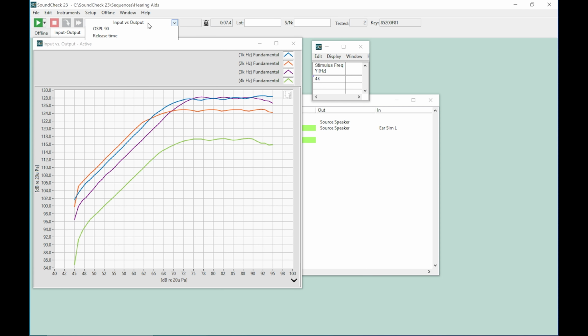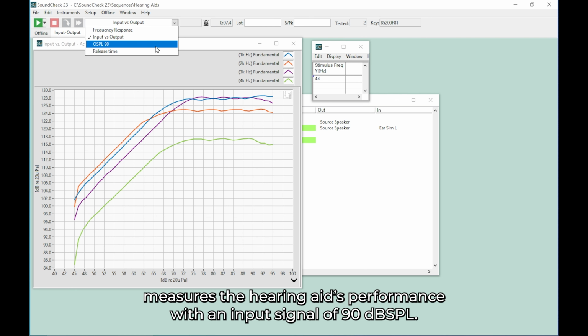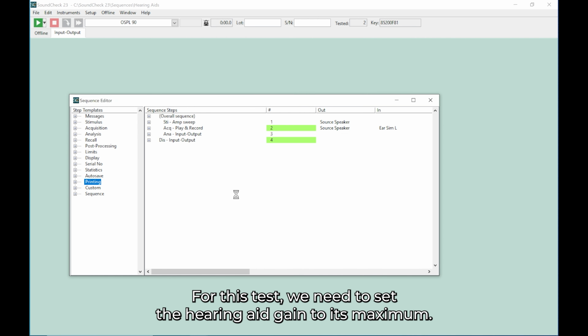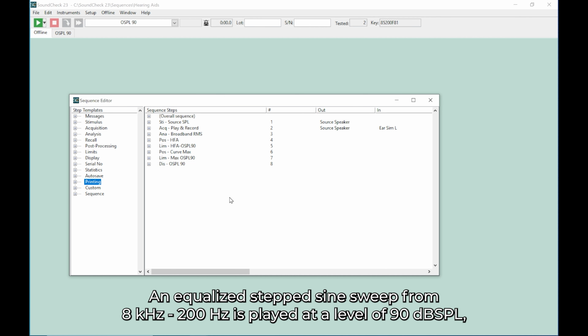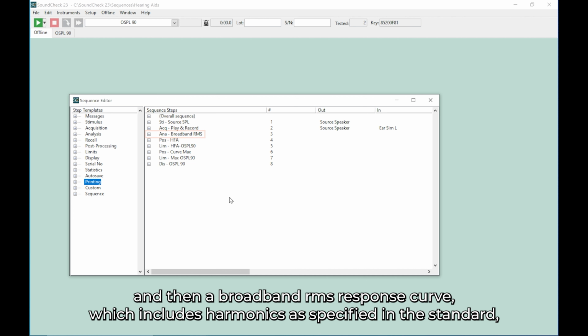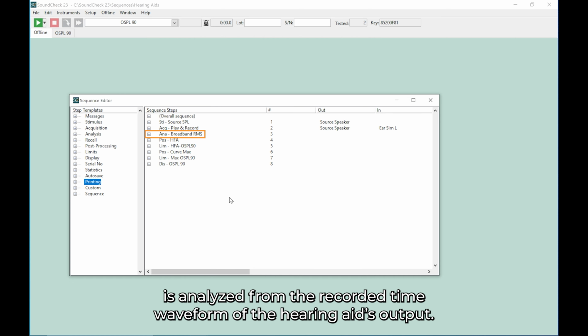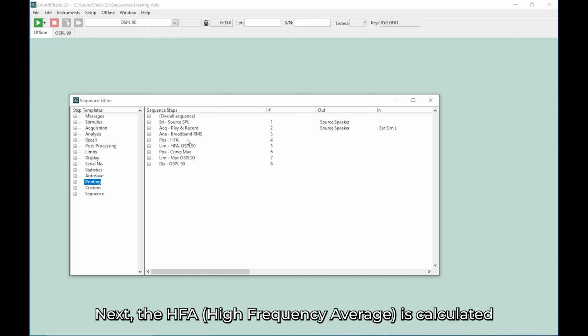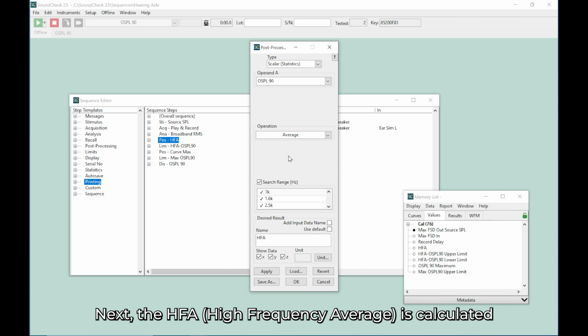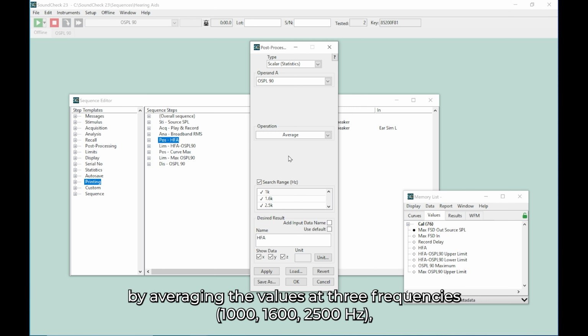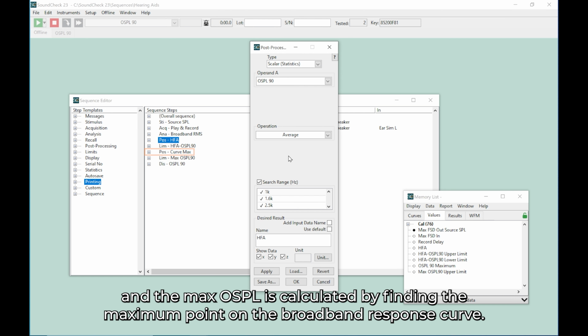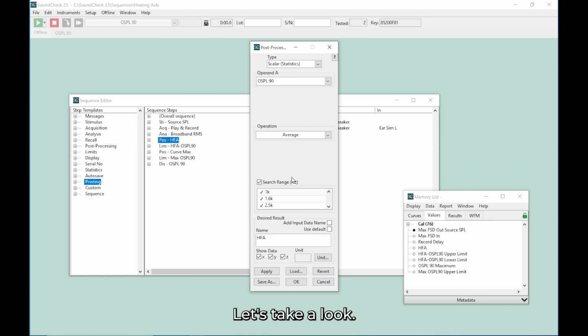The OSPL90 test measures the hearing aid's performance with an input signal of 90 dB SPL. For this test, we need to set the hearing aid gain to its maximum. An equalized step sine sweep from 8 kHz to 200 Hz is played at a level of 90 dB SPL, and then a broadband RMS response curve, which includes harmonics as specified in the standard, is analyzed from the recorded time waveform of the hearing aid's output. Next, the HFA, or high frequency average, is calculated by averaging the values at 3 frequencies: 1000, 1600, and 2500 Hz, and the max OSPL is calculated by finding the maximum point on the broadband response curve. Let's take a look.